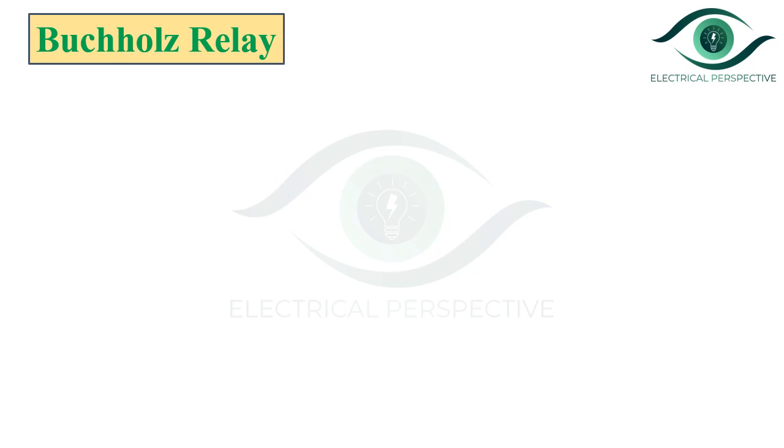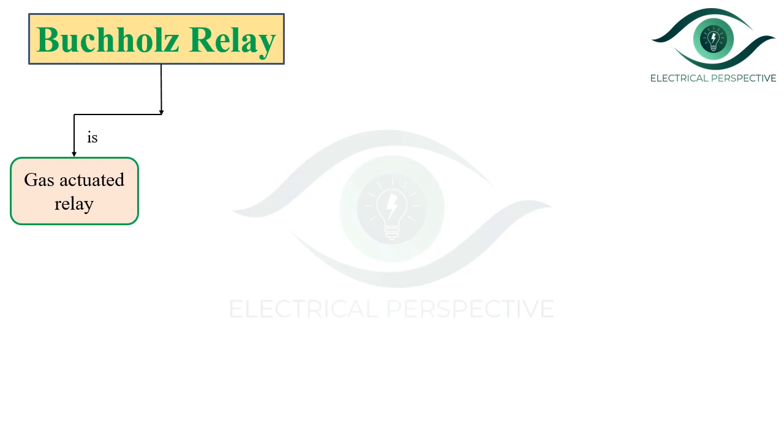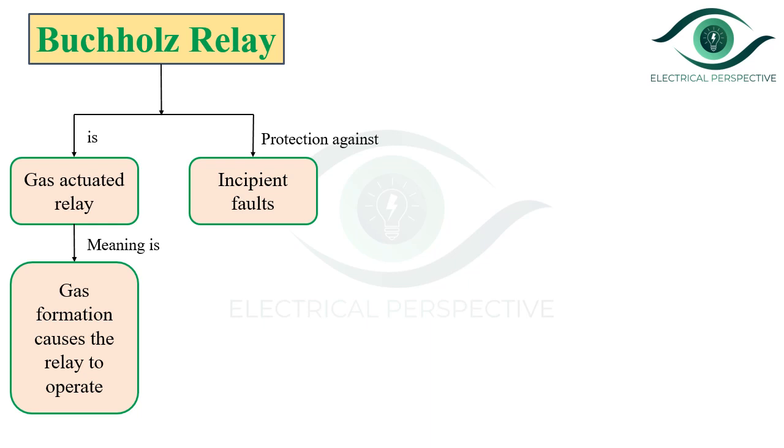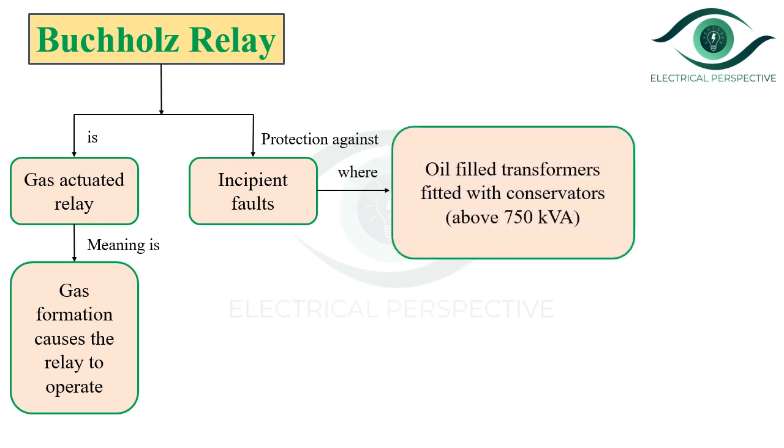Let us discuss some basics of the Buchholz relay. Basically, it is a gas-actuated relay, meaning that gas formation causes the relay to operate. It is used to provide protection against incipient faults in the case of oil-filled transformers fitted with a conservator having a rating above 750 kVA. It is generally uneconomical to use the Buchholz relay for transformers having a rating less than 750 kVA.